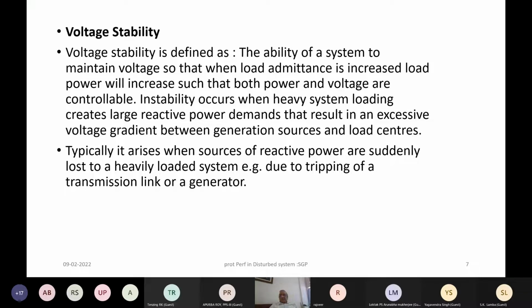We'll just revise some of the concepts. When we talk about voltage stability, it's the ability of the system to maintain voltage so that when the load admittance is increased, load power will increase such that both power and voltage are controllable. Instability occurs when heavy system loading creates large reactive power demand that results in excessive voltage gradient between generating sources and the load centers. And we have seen some of the load versus voltage curves with that typical nose shaped curve, where the voltage collapse phenomenon occurs after a particular point and then the total collapse takes place.